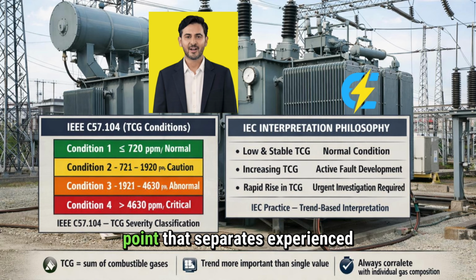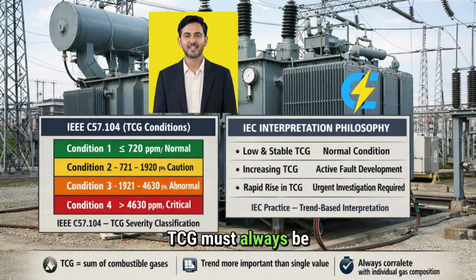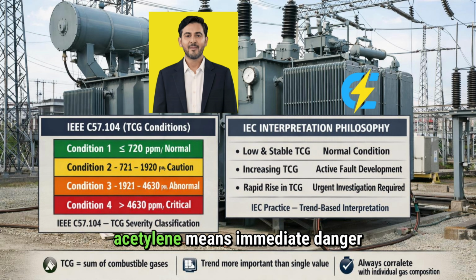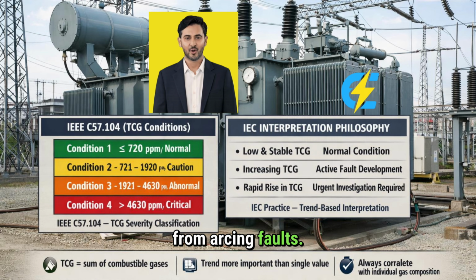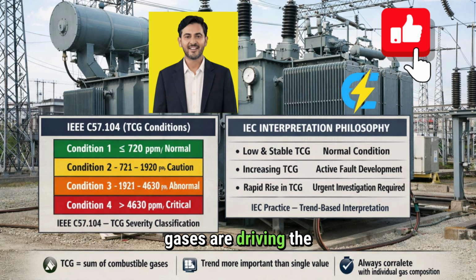But here's the key point that separates experienced engineers from beginners. TCG must always be interpreted with individual gas composition. This is the heart of TCG interpretation. High TCG dominated by carbon monoxide means aging of cellulose insulation. High TCG dominated by acetylene means immediate danger from arcing faults. The same TCG value can represent completely different scenarios depending on which gases are driving the increase.